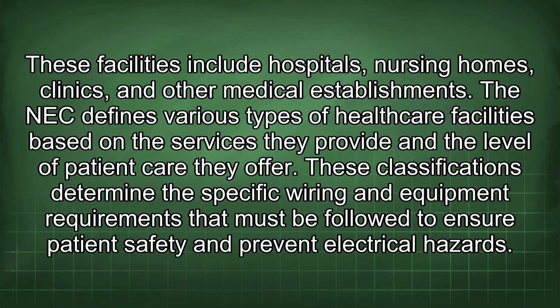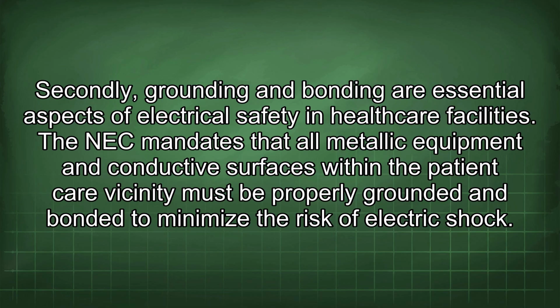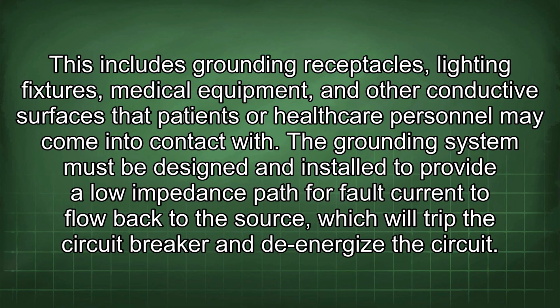Secondly, grounding and bonding are essential aspects of electrical safety in healthcare facilities. The NEC mandates that all metallic equipment and conductive surfaces within the patient care vicinity must be properly grounded and bonded to minimize the risk of electric shock. This includes grounding receptacles, lighting fixtures, medical equipment, and other conductive surfaces that patients or healthcare personnel may come into contact with. The grounding system must be designed and installed to provide a low impedance path for fault current to flow back to the source, which will trip the circuit breaker and de-energize the circuit.